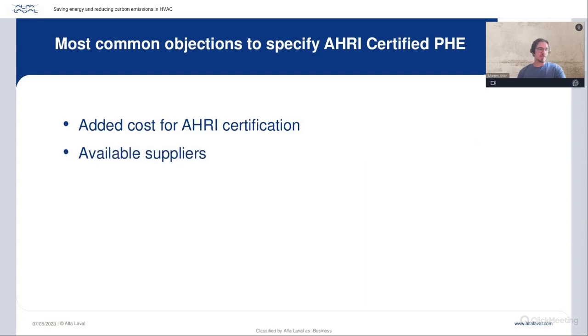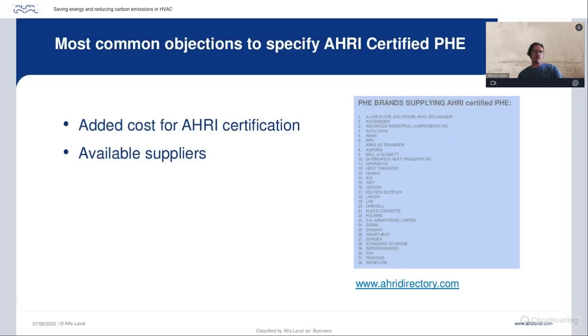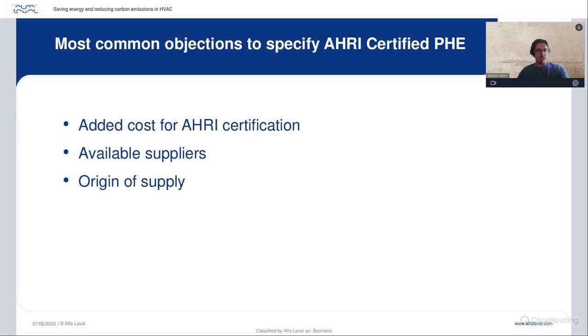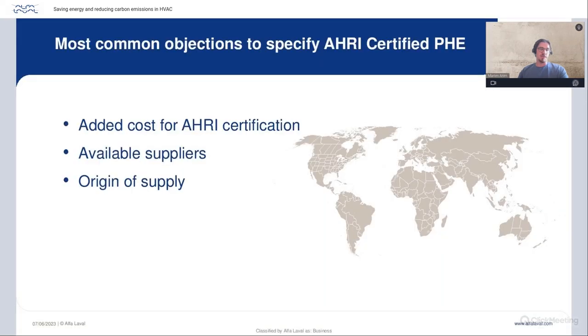Secondly, many times we hear that, okay, this is a brick wall. There are only a few suppliers available, and then I will feel very limited. But right now there are 32 suppliers available, I would say, in the European market. All of the major suppliers found in the market are members of the certification program. And you can find all suppliers in this link below, ahridirectory.com. You can scroll down to LLHE, Liquid to Liquid Heat Exchanger Certification Program, and you will find all suppliers available there. Regional supply is also something that I hear, maybe not in the European market, but others. And of course, there is no limitation, as we can supply from manufacturers around the world. That is the beauty of this. AHRI is verifying that the design is correct. And then if you deliver the same unit from any factory, that is what they are going to check and verify.